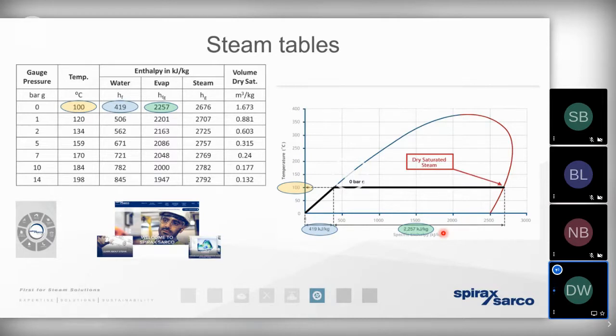What you may recall from previous presentations in the series is that if we're distributing steam that is not perfectly dry, it's far more likely that that steam will condense out in the distributing pipework. In other words, we're going to have a massive amount of condensate that needs to be removed from the infrastructure. It's also representative of a distribution inefficiency, because we're going to get less steam finding its way to the process than the boiler's actually producing.